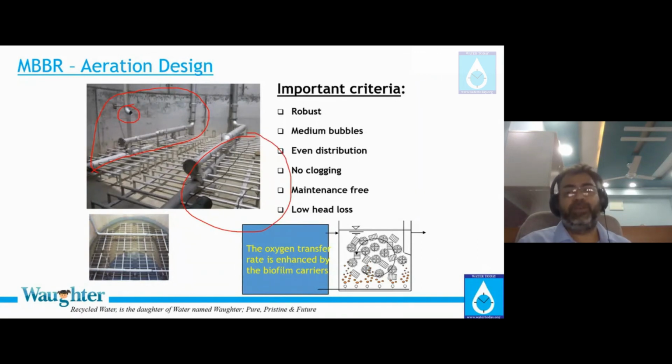So the media is continuously recirculated both in this direction as well as in the other direction, right? And in that process, you also have to continuously avoid clogging. That means the screen plays a very, very important role in where they are exiting. So how you enter the water, how you exit, how the bubble is moving, and how the carrier is moving: these four combinations are the know-how for this design. Once designed well, it is a beautiful technology.